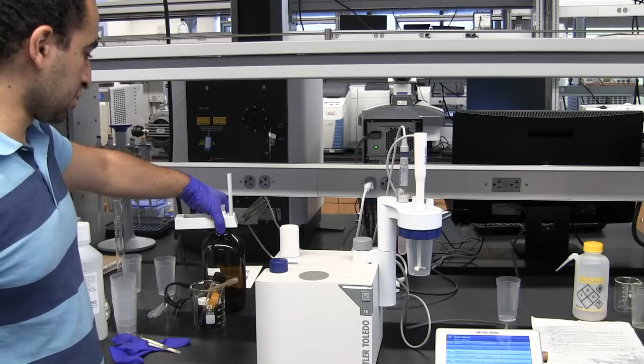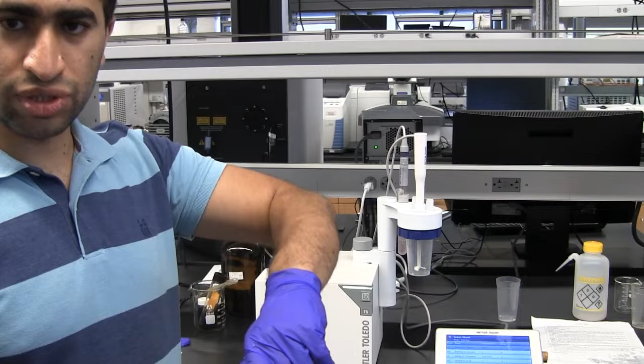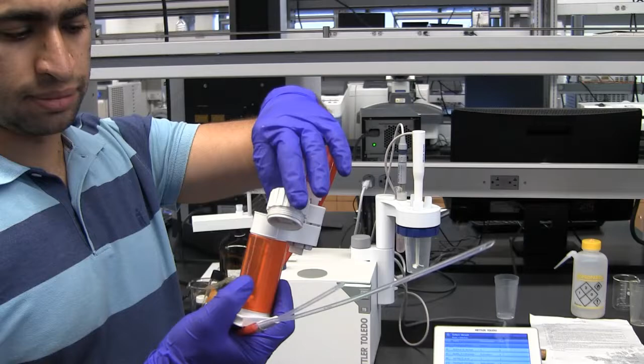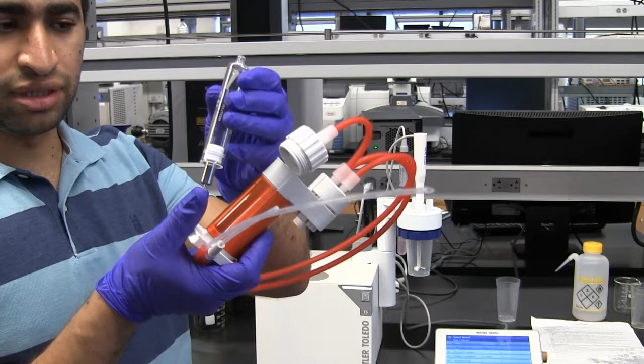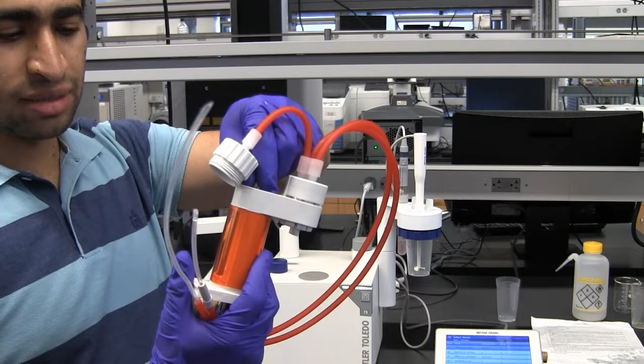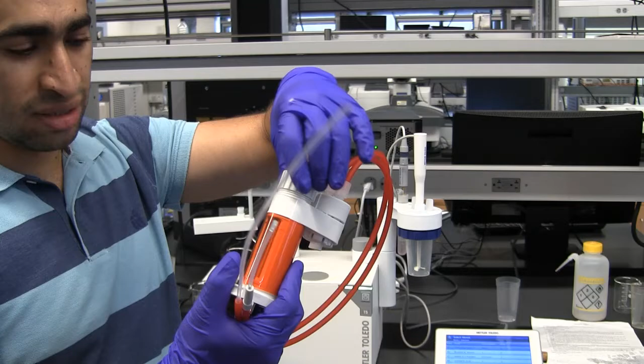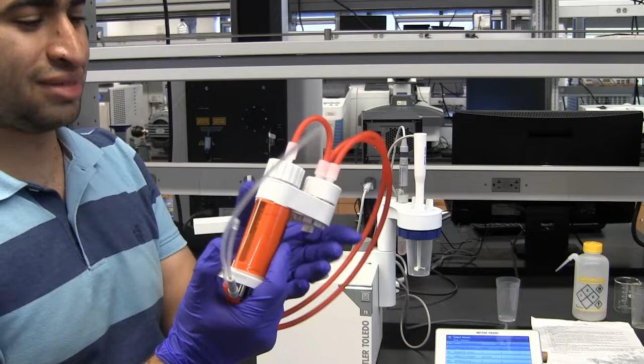Okay, so now I changed the titrant in this bottle into KOH, and in order to clean this out, as we said, we did the 3 cycles, and then we took our glass bottle out, and then we took the piston out of here, cleaned it with water, and then put it back. Taking the piston out could be a hard task, so it may need a little bit of force, but try not to break it, because we don't have any extra parts.